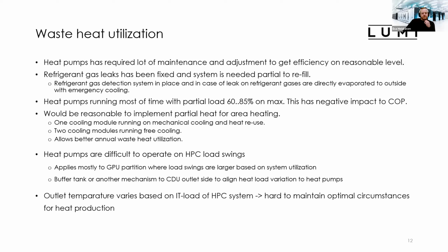And another issue is that with the partial heat flow, heat pumps are running most of the time with partial load, so 60 to 85% of the maximum load, and this has a negative impact on the COP. There have also been some leaks.